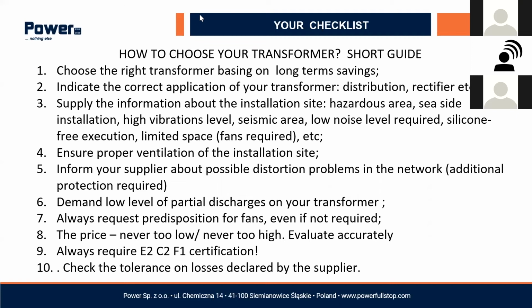And second point: when buying a distribution transformer and using it also for a 6-pulse converter, consider that at least you have to add an electrostatic screen between the primary and secondary voltage. This already protects your transformer a little bit from the harmonic content coming from the grid.